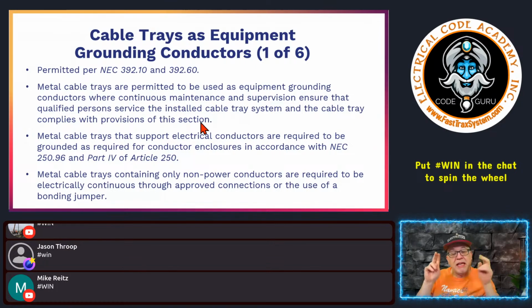You cannot use the cable tray as an equipment grounding conductor unless it's in a location that has constant, continuous maintenance and supervision and ensures that only qualified persons will service it. That means they have a staff. That means they have people that are dedicated to the maintenance and upkeep, and they're the ones that are going to be working on it. A lot of people will argue and say, well, couldn't it just be when I hire an electrician to come in? That's not maintenance and supervision. That would be calling in to do contract work, that type of thing. So it is a difference in looking at how you do it if you're going to use it.